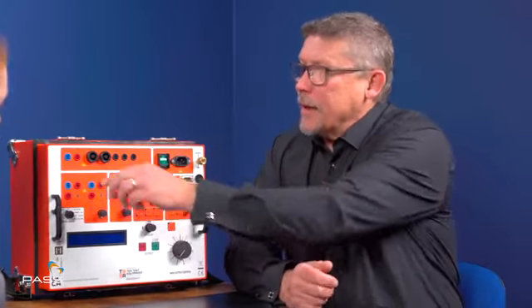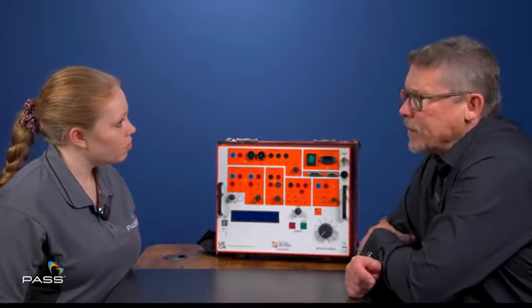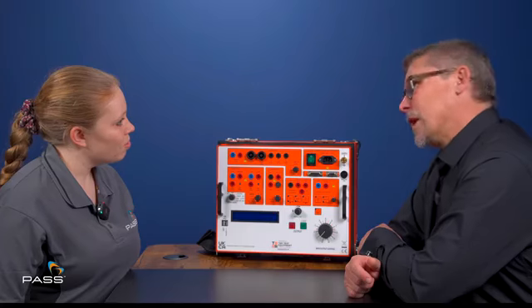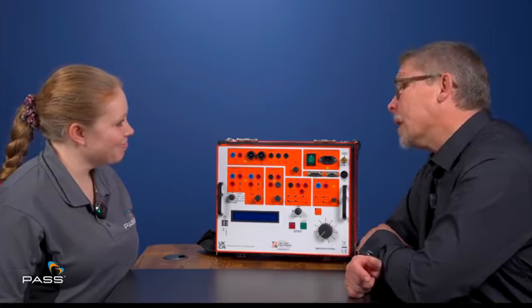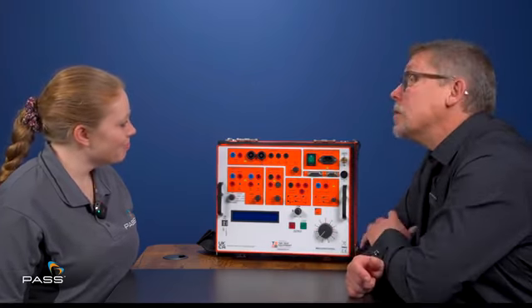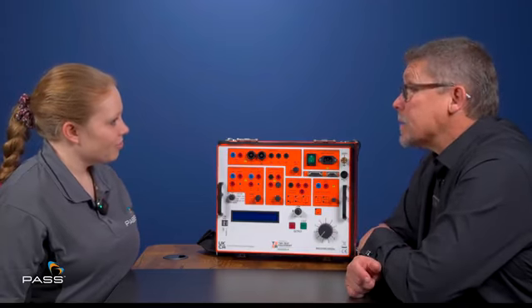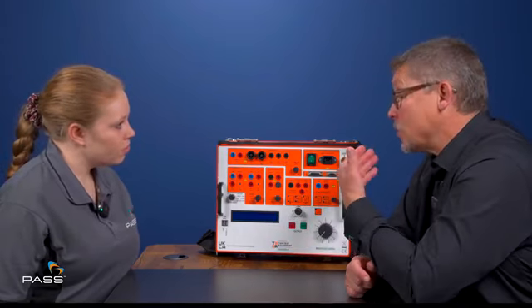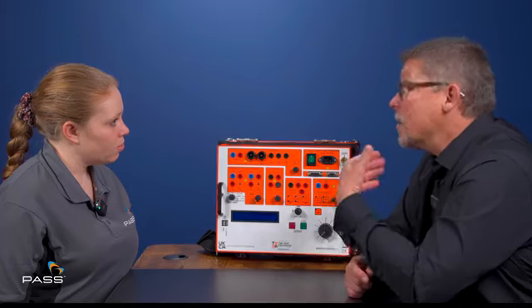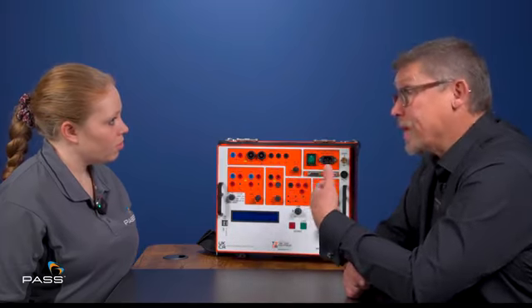So the first thing about it is, I mentioned here, we got a tap here that will give you 200 amps for 6 seconds. Many engineers out there will be thinking, hang on a minute, that's not secondary injection, that's primary. And yeah, it is. We can actually use this to operate a main circuit breaker up to 200 amps because we got 200 amps for 6 seconds. Most circuit breakers are going to operate within a second, and therefore we can operate that circuit breaker, but we can also time it.